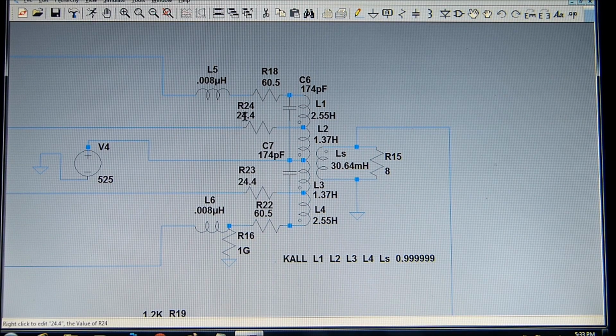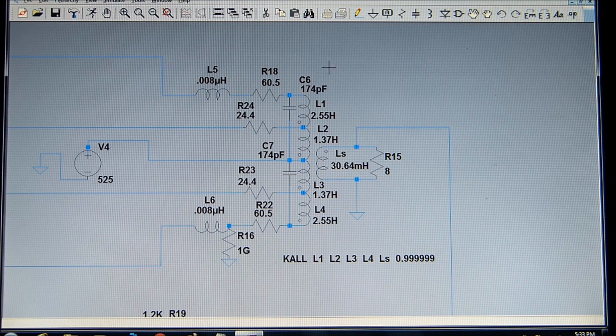The nice thing about the GR instrument is it gives us the Q, and Q is the reactance over the resistance. So I've measured the resistance across half, and then I measured the resistance across this half, and I assumed it was capacitive reactance, so I came up with 174 picofarad shunt here and 174 picofarad shunt here. Now you can take this thing to the level of insanity, and you can put some off the ground, and then you can put another one off the ground, and then you can try to shunt some between them, and you just got to figure out at some point just how insane you want to make yourself. But these transformers actually model really fine and don't take up your whole life.